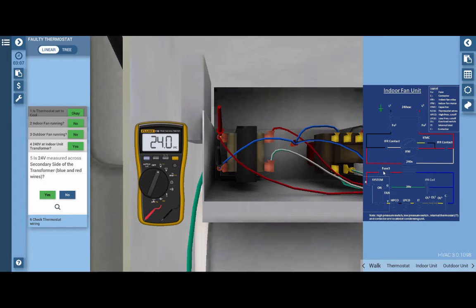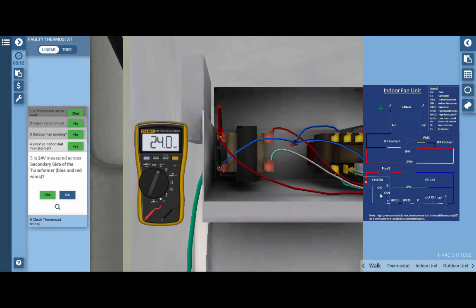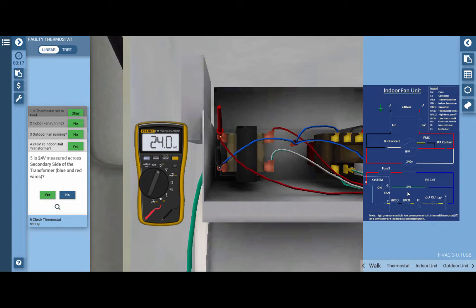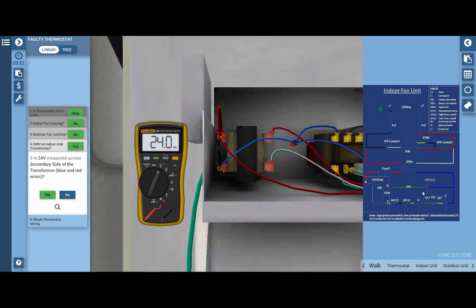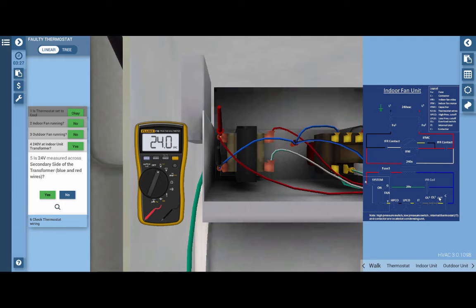We have a little fuse here, but we also have the thermostat. Now, whatever is causing the indoor blower motor as well as the outdoor fan motor and compressor to be off, it has to be something common to both of these or all three of these components. And as we can see here, the indoor fan relay coil and the compressor contactor are both controlled by the thermostat. So our next step is to check the thermostat.